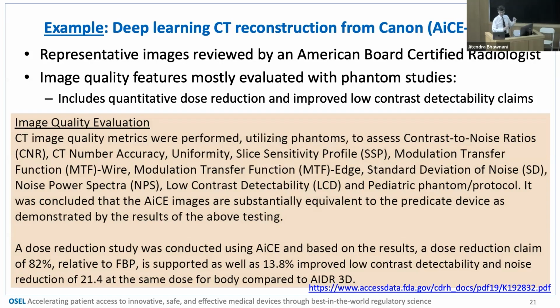It doesn't mention a full clinical trial, but the radiologists evaluated the images, and there were also a lot of phantom studies, the image quality phantom studies that were done. I will read it because I'm sure you're interested. Phantoms were used to calculate contrast to noise ratios, CT number accuracy, uniformity, slice sensitivity profiles, the modulation transfer function with a wire, the MTF with an edge, the standard deviation of the noise power spectra, and the low contrast detectability with the phantom that we talked about before in the iterative. Some pediatric protocols were also tested in phantoms. So that was the evidence. That's the kind of evidence that we review, which is very familiar to you, similar to what you need for publishing a good paper, or it's well known in our field.